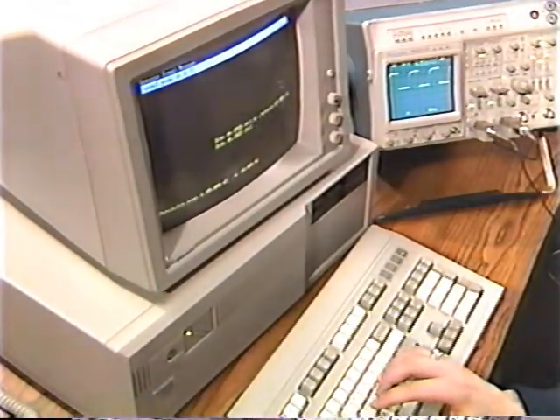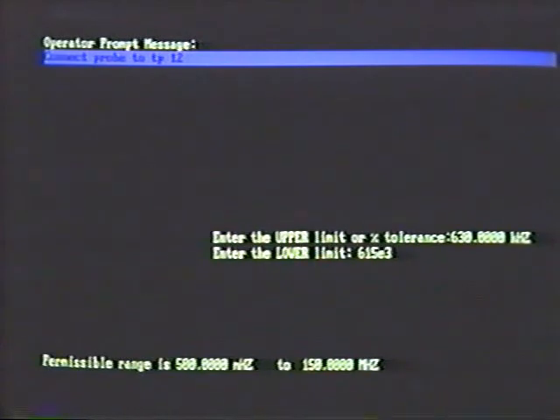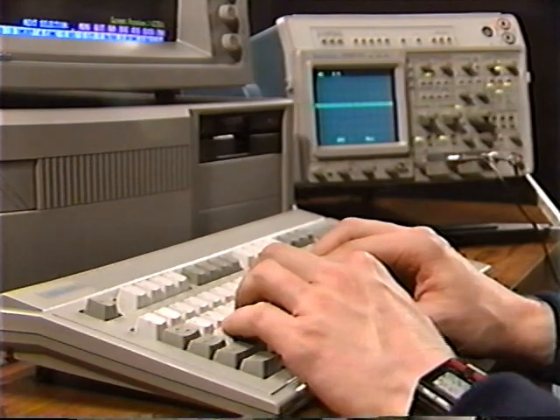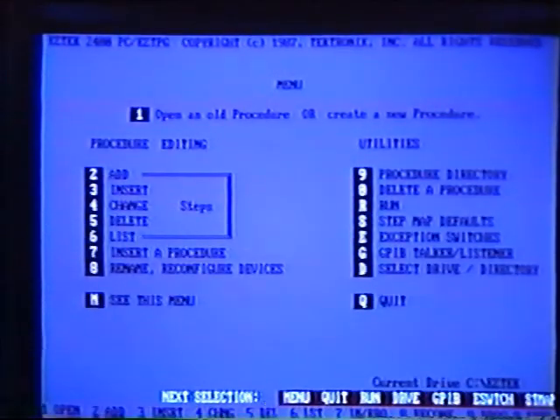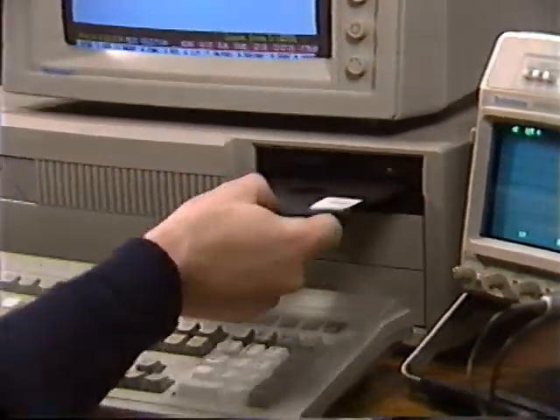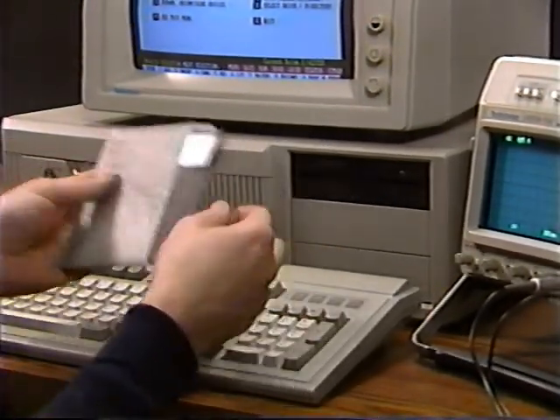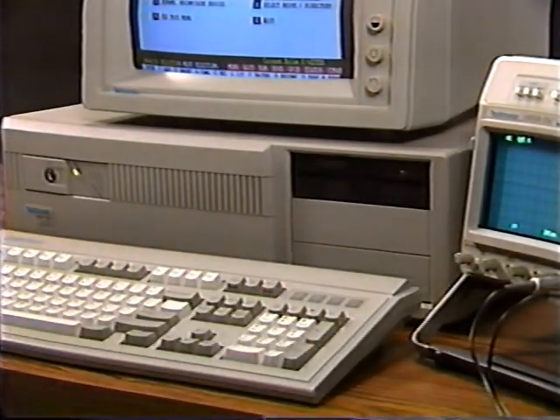Next, we'll enter the operator prompt and describe what the operator needs to know, like which probe to connect to what test point and its location. We'll enter the high and low limits for the measurement. If the measurement fails, we can branch to a troubleshooting or calibration procedure. This provides flexibility, but at the same time, locks testing into a pattern the experienced station engineer knows to be the most efficient path to target a problem. Now we've added a new step to the procedure using the EZtest program generator. The finished procedure can be stored on a disk to be recalled later by the operator, who will use the Easy Execution module for this calibration procedure.